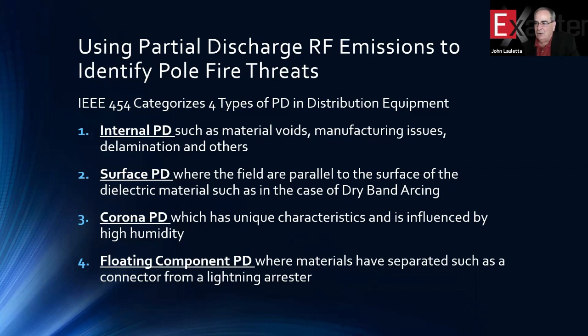and it goes into what they call dry band arcing as a precursor for high leakage currents that contribute to pole fire issues. Corona PD is one that we don't use in our evaluation of deteriorated equipment because it's so influenced by humidity. And most of our work is at 34.5 kV and below anyway, because we're working with distribution utilities in most of our deployments. And there's really no corona at that level and below. But when you do have corona as an indicator of partial discharge, got to be very careful, because it can simply be high humidity that's causing that corona to be developed.